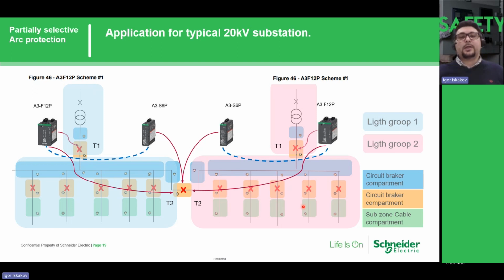But here we can build partially selective protection when we protect the left side of our substation. In case of arc flash, we will have a trip on the incomer and the bus bar circuit breaker, but the right side will stay in work. In opposite, if any arc sensors activate on the right, we have extremely fast tripping on our units, and we can protect the right part with the left part of our substation working.